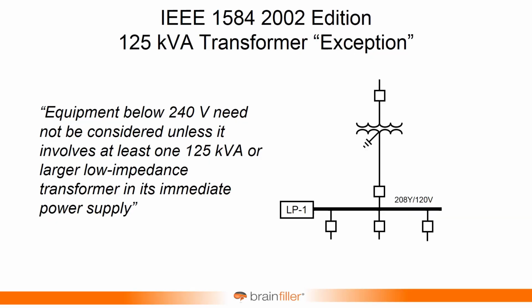Okay, the question that everybody keeps asking. There was language in the 2002 edition of IEEE 1584. It actually appeared in two different locations that stated that equipment below 240 volts, which kind of implied 208, doesn't need to be considered unless it involves at least one 125 kVA or larger low impedance transformer in its immediate power supply. So the size of the transformer, what that had to do with it, is the thought was smaller transformers are going to reduce the short circuit current. And if this is down at 208, there were just a couple of tests that were performed that indicated that it's really going to be difficult to sustain. So can you have an arc flash? Yeah, but is it going to sustain and be what at the time was considered to be a significant hazard? No, not really. And so that's why this language was included.